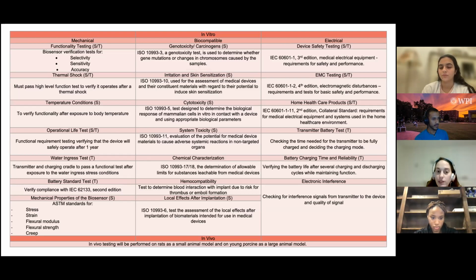To continue with the electrical testing, this is essential to admit the device as safe to operate inside the body. First, we will start with testing the general device safety, ensuring the device will operate under specific electrical conditions, such as the signal from the transmitter to perform its intended function. This will ensure that the inductive coil and the transducer will not cause any harm inside the body. EMC testing will be performed as well for any electrical and electromagnetic signaling interference to or from the device.